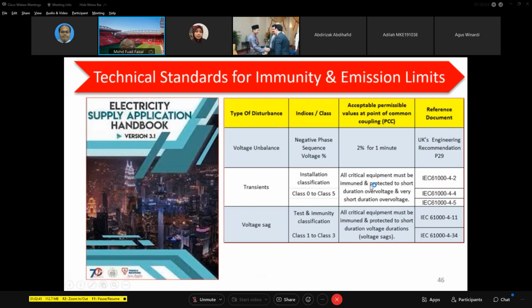Okay, the next element is unbalance. This is also very important. That's why the consultants and engineers must understand. One is to protect their own customer requirement. Secondly, it is to protect other customers. We don't want a steel mill, every time it operates, to introduce unbalance to the customer and to neighboring sites. So we don't want that to happen. Even in the case of transient, we want proper protection against transient. We don't want the customer equipment to be damaged by transient due to lightning.